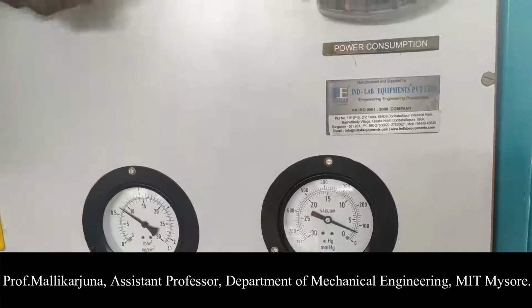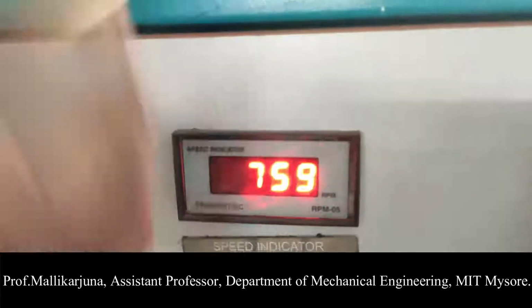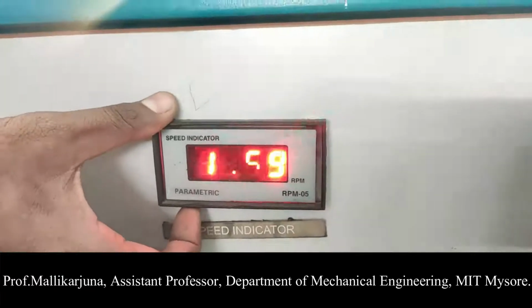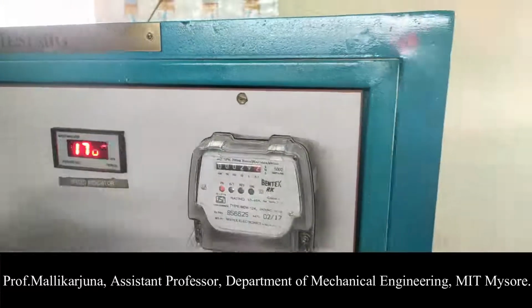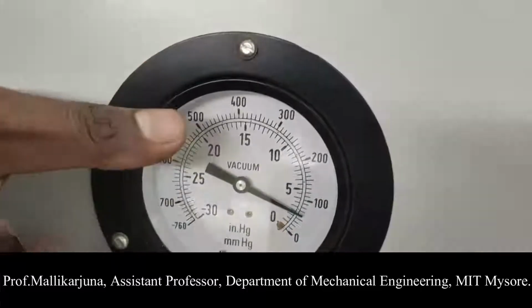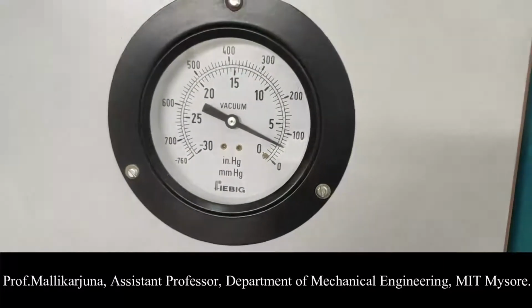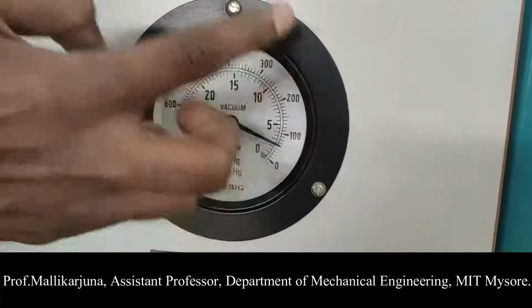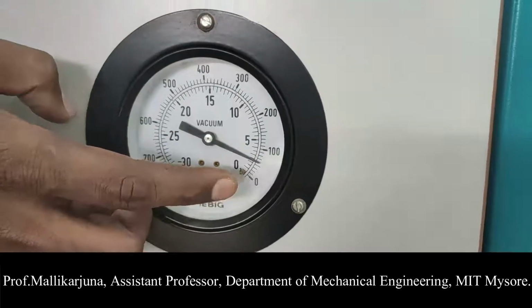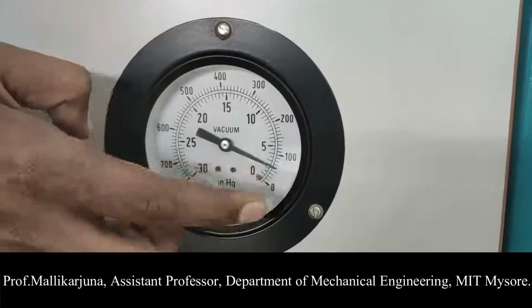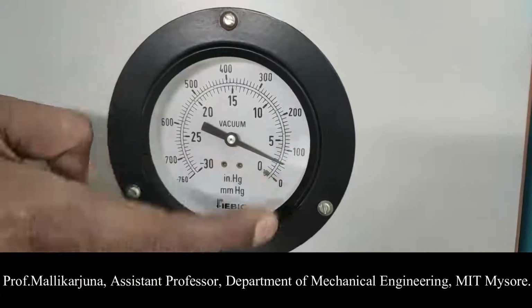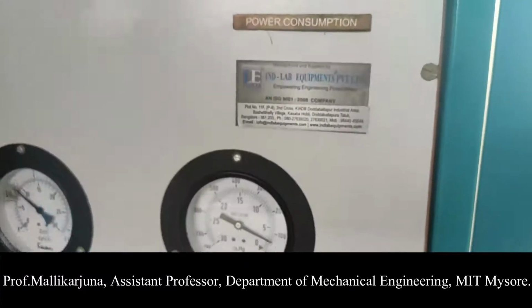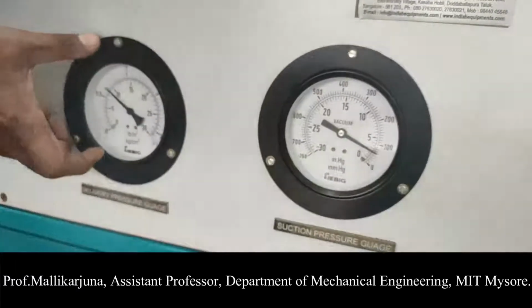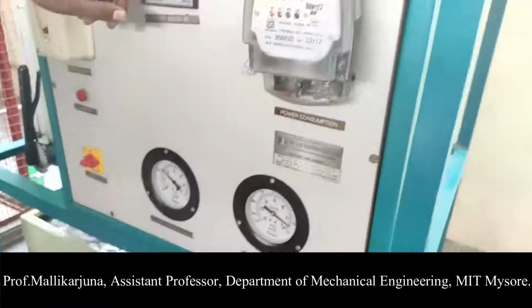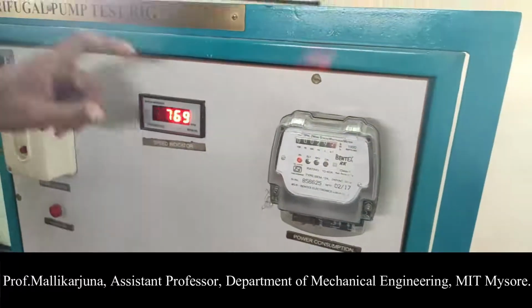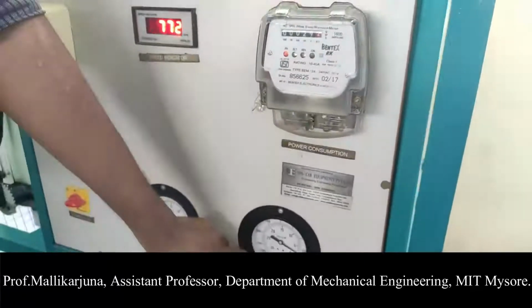For this delivery pressure, this is the speed with which the motor is supplying the energy to the pump line. So now this is the suction pressure that has been created for the delivery pressure we have set up. Please note down this value also. The outer reading we need to take down. This is in between 0 to 100. So almost the value is 50 mm of Hg for 0.6 kg per centimeter square delivery pressure. So now we are aware of the speed with which the motor is supplying the energy to the pump, the delivery pressure as well as the suction pressure.